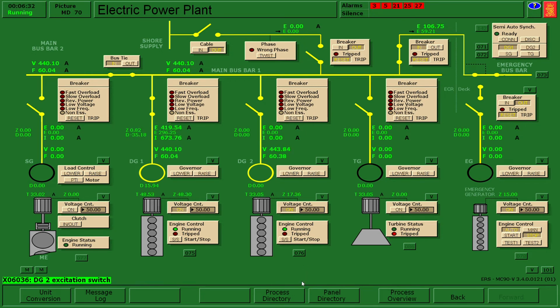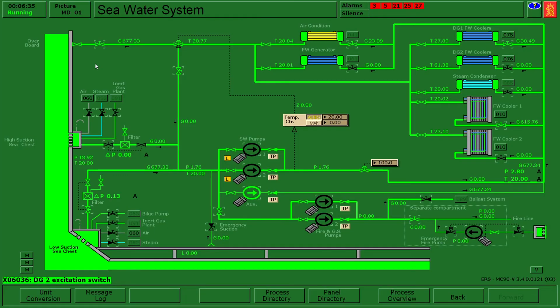And then we're gonna proceed to MD01, our seawater system. And then we're just gonna go ahead and open our cooler valve going to the diesel generator number 2, as well as our main freshwater cooler shut-off valve. Okay. So once that's opened, we're just gonna start our seawater pump and then set the remote, both pumps.